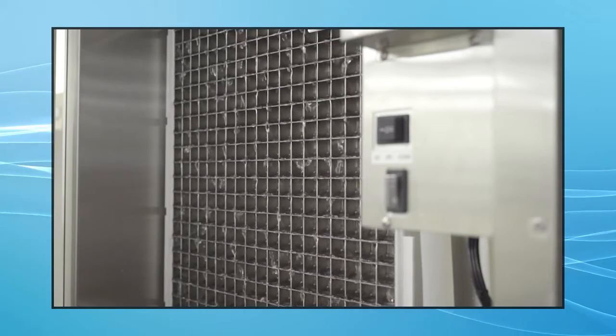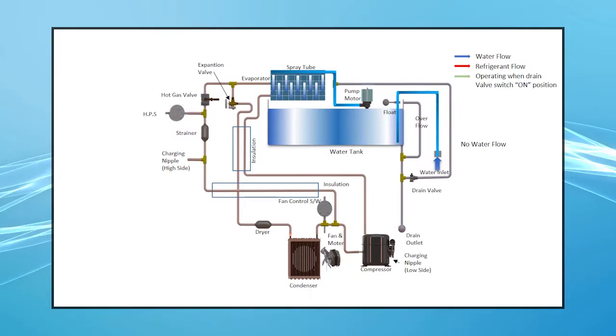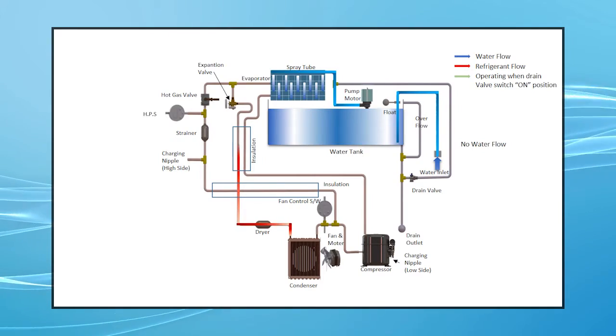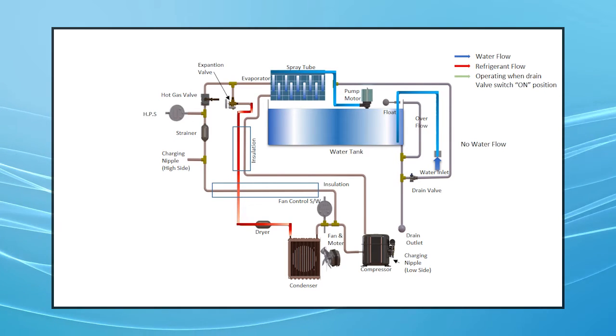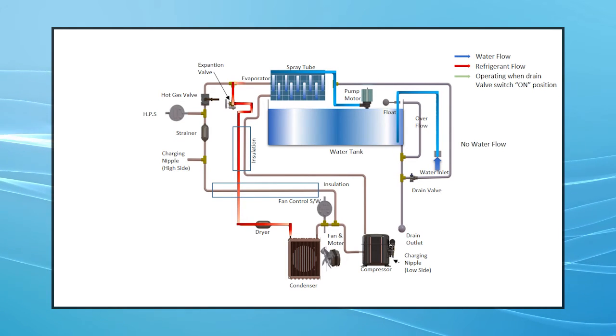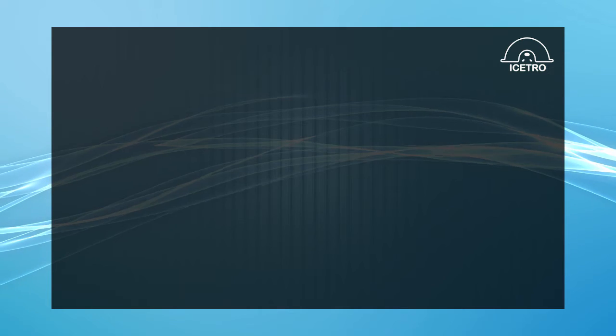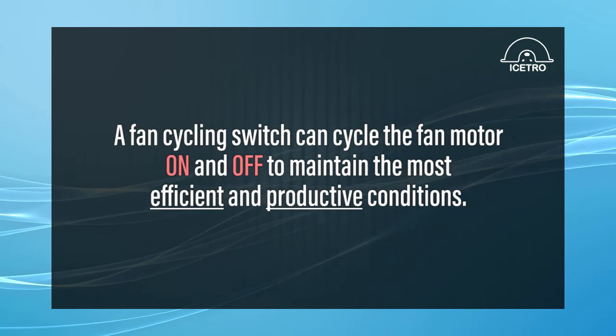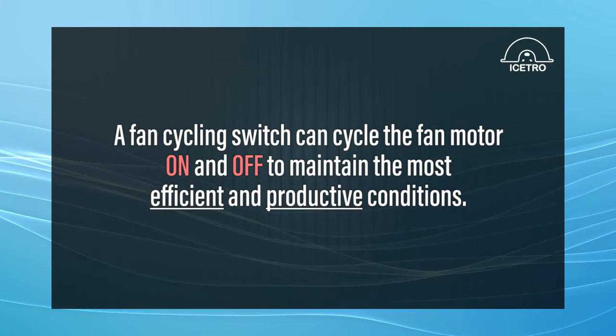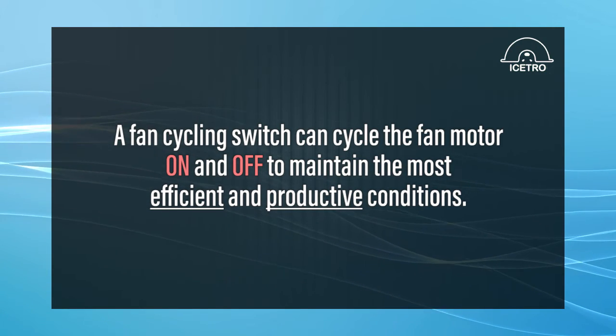Then, the hot gas solenoid is energized to equalize pressure. The machine will then start the freeze cycle. The water pump is now pumping water across the evaporator, and the condenser fan motor is operating. A fan cycling switch can cycle the fan motor on and off to maintain the most efficient and productive conditions.